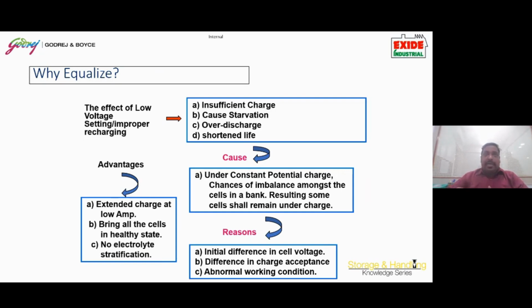So equalizing charges also help you mix the electrolyte. The top water and the electrolyte mix and maintain a homogeneity inside the cell. If electrolyte stratification happens, then whenever there is a load coming on the cell, it most of the time fails to provide backup, because it does not have a uniform chemical reaction over the surface area of the positive plate and the negative plate. The lower part of the positive plate will have a higher rate of reaction, while the upper part will not have any reaction at all, due to the stratification. So this is one terminology I just wanted to explain.